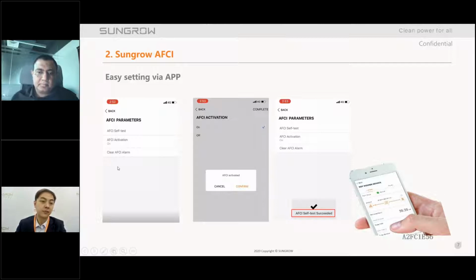When an arc is generated, the system will give you an alarm on the main page. Every time you open the application, if there is an arc problem, it will show on the main page. Then you'll know what happened, and the inverter will cut it off, but it will restart after 5 minutes. If the arc is still generated, the inverter will cut it again.